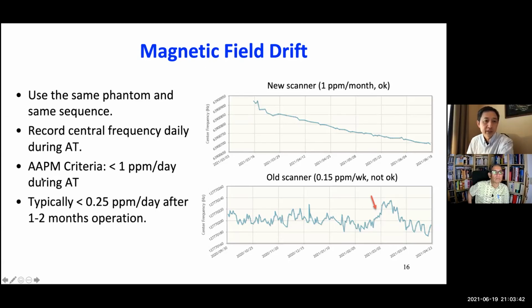This is the AAPM criteria. It's 1 ppm per day during acceptance testing. So on top, I'm showing you a new scanner we installed in about March. And then you can see the central frequency gradually change. So the magnetic field gradually changes.